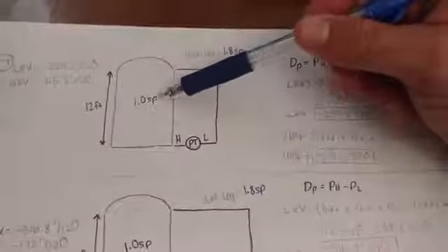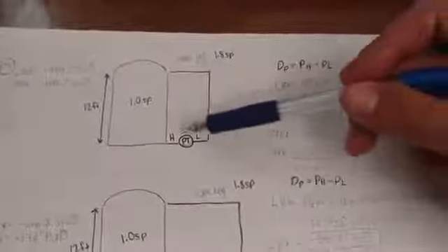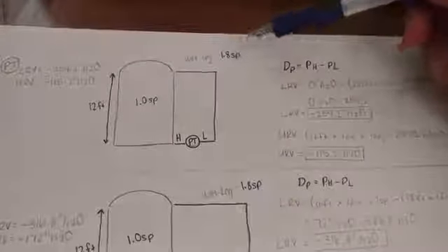So let's get started. In this situation up here, we have a tank. It's filled with water. We know that because the specific gravity is 1, and it's 12 feet high. And we have a wet leg over here that has a specific gravity of 1.8, so we know it's more dense than water. Alright, here's our pressure transmitter, here's our high side, here's our low side. So, let's find the upper range value and the lower range value.